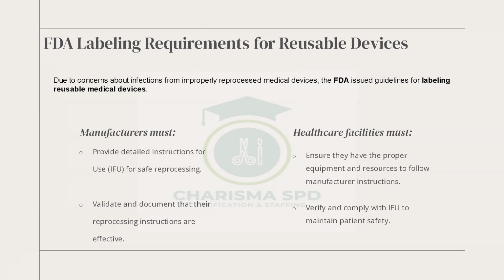And hospitals must ensure they have the proper equipment and resources to follow the manufacturer's instructions. Okay, you must provide that. And then another requirement by the FDA on the part of the manufacturer is that they should validate and document that their reprocessing instructions are effective. They must have a document to show that the instruction they are giving for reprocessing the instrument or the device is effective. Okay, very, very effective. The processes they have outlined should not lead to the malfunction of the instrument or the device. It shouldn't lead to decolorization of the instrument or cause any injury of any sort.